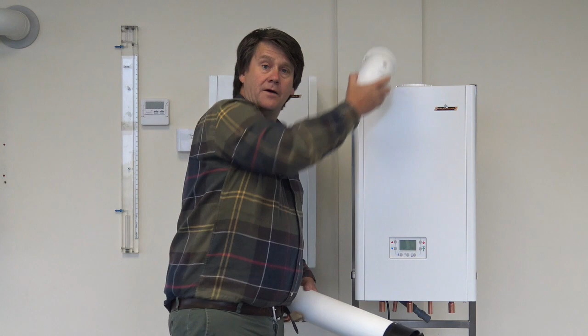Off the top we have the boiler bend, which fits directly onto the top of the boiler. So you haven't got the deep flue header with the test points incorporated in it. Nothing wrong with that system, but the only negative is the height of the boiler, you lose distance from the ceiling. For us, it's better to have the bend inserted onto the top with the test points incorporated on the bend, giving you more play with your ceiling height.